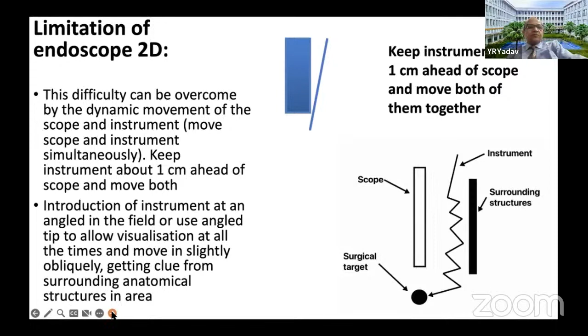There may be difficulty in orientation. The camera may rotate. The camera should be placed in the correct position. The orientation should be checked by anterior, posterior, or side movement. On the camera head, usually the button should be towards the monitor. The image should be seen as it is seen in open surgery. When you do surgery, the camera can rotate, so keep checking, because if it rotates, then the whole orientation will go wrong. So you may cause problems. So keep watching the camera position.